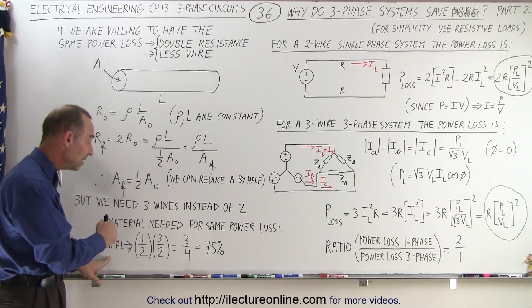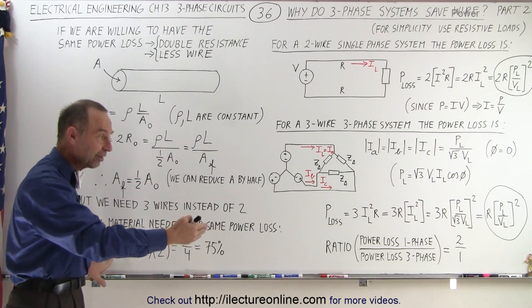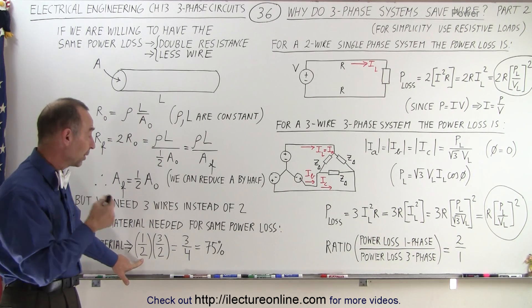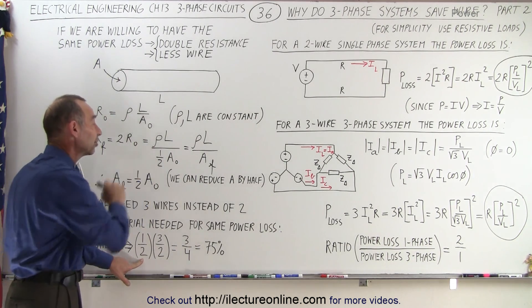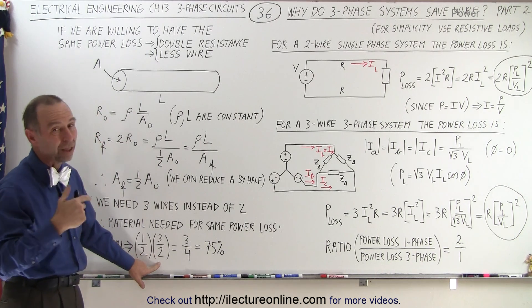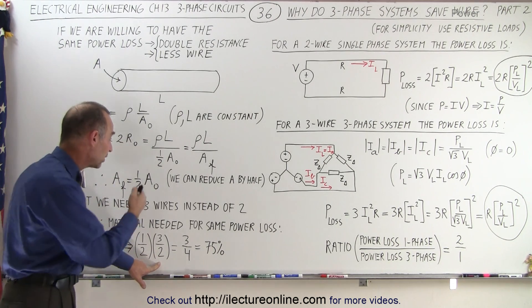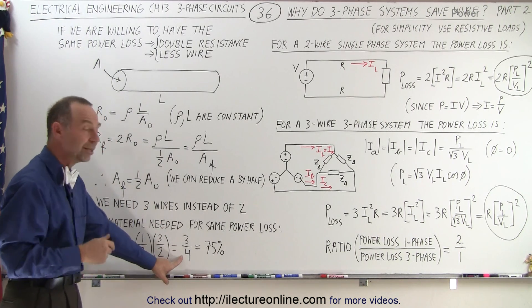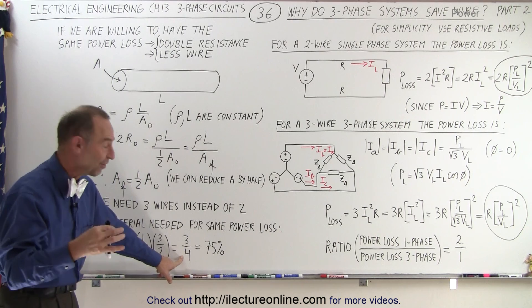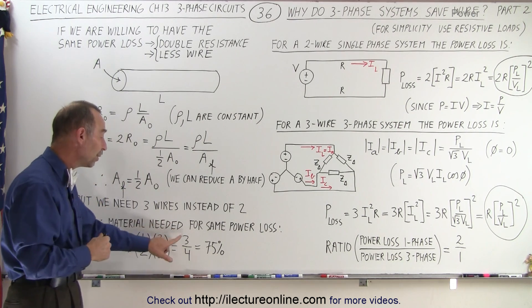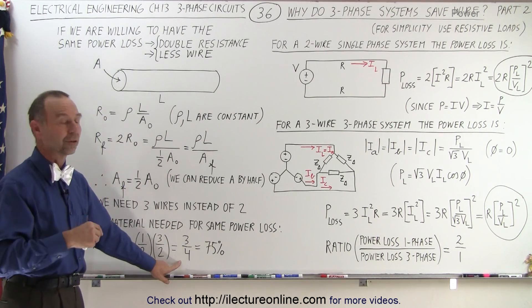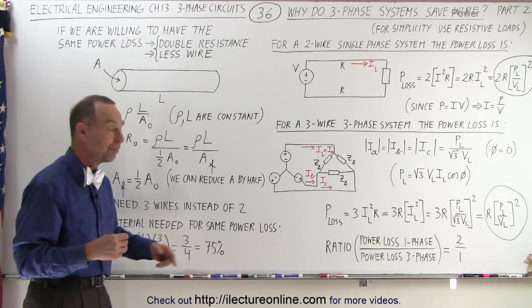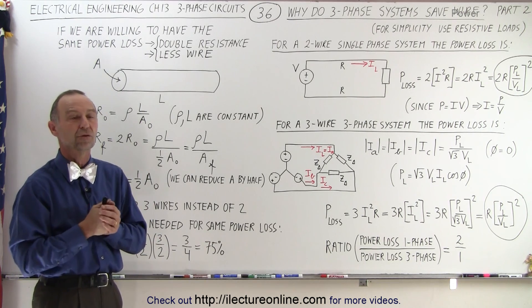So finally, the amount of material we're going to need for a three-phase system with the same power loss as a one-phase system: we only need half as much material because we only need half as much of the cross-sectional area, but we need three to two amount of wires. When we multiply that together, the amount of material we're going to need for a three-phase system versus a one-phase system is three-quarters of the original material. We only need 75%, so we have 25% savings on material used.